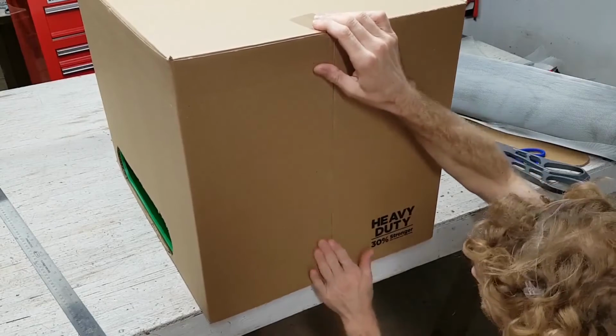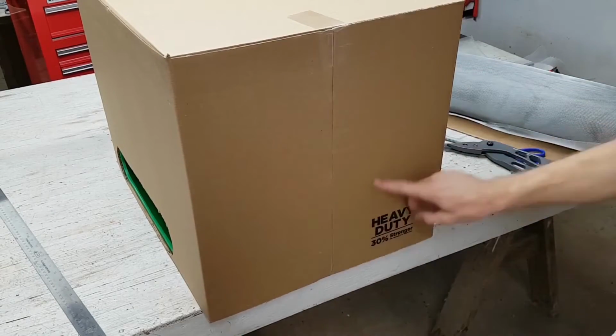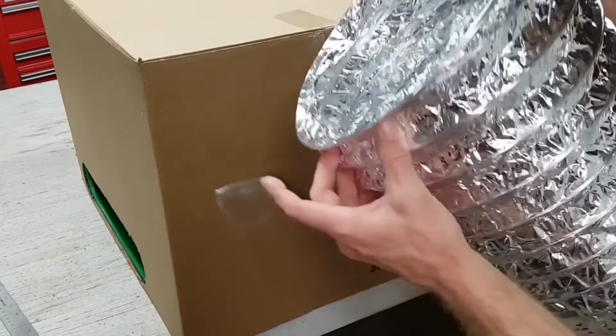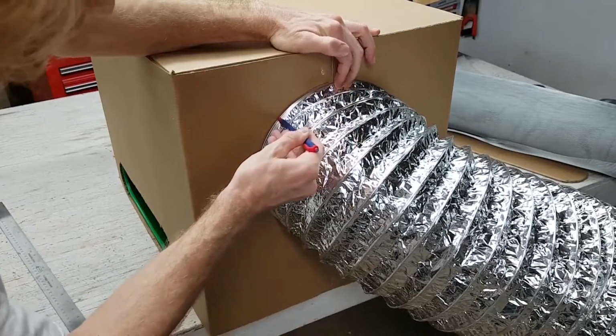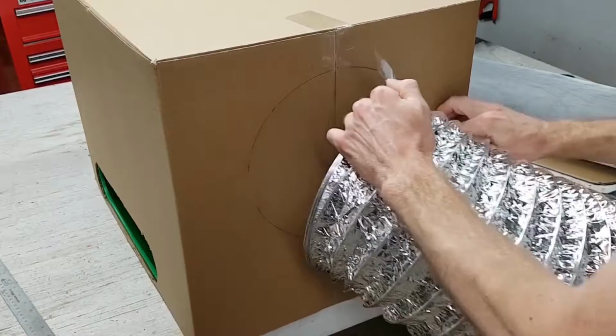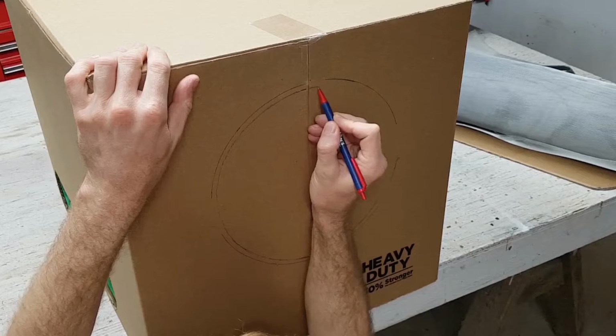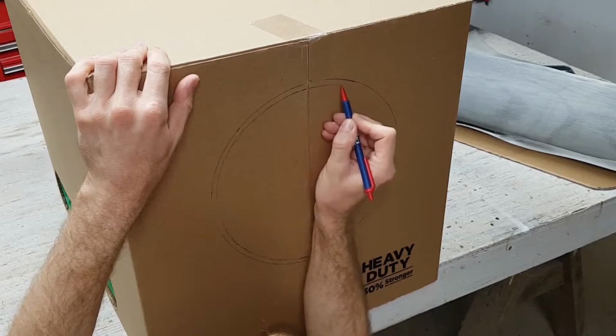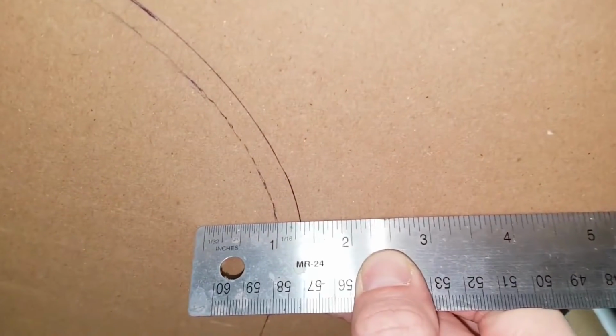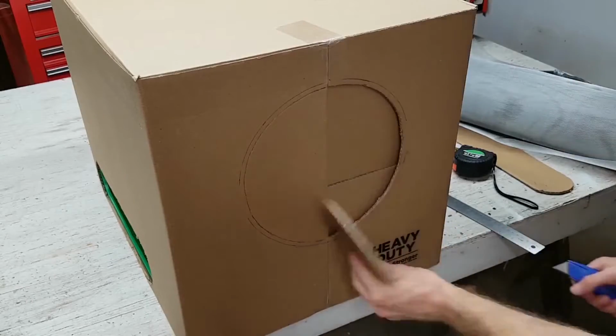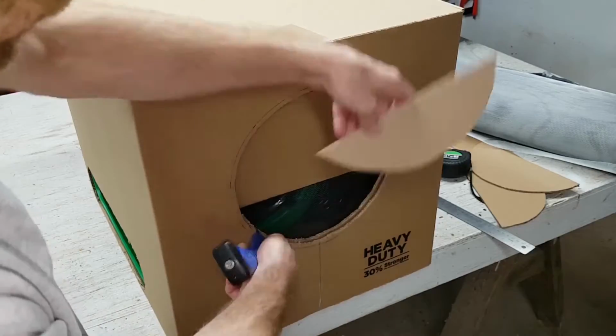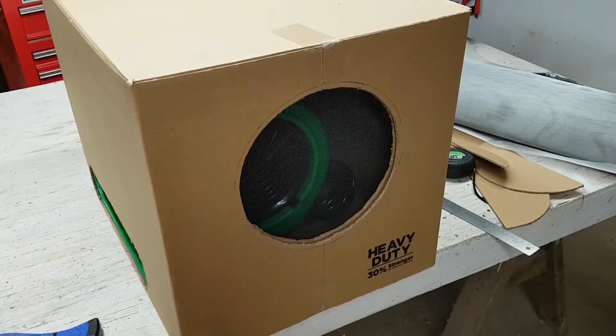After closing this end and temporarily taping it shut, I use the foil duct to mark where the opening is needed. I then make another small circle just inside the first one. The smaller circle is my cut line. The opening for the duct vac hose is carefully cut with a utility knife.